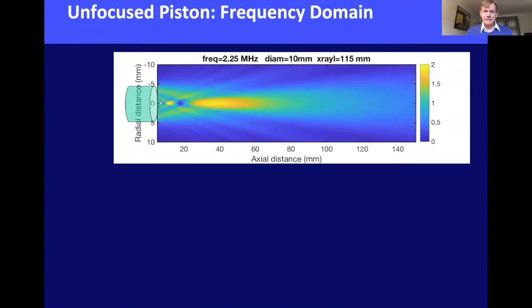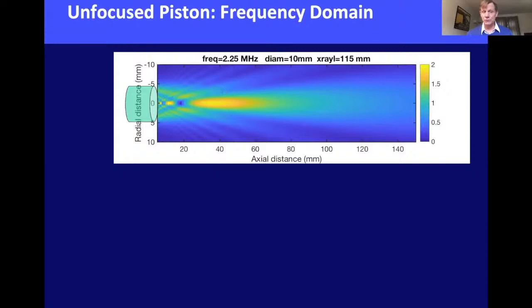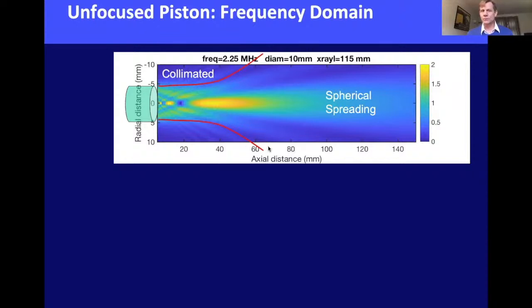For an unfocused piston in the frequency domain using the Rayleigh-Sommerfeld integral, an example for a 2.25 MHz transducer with 10 mm diameter shows a beam of sound emerging with spreading in different directions — not a simple plane wave. There is a near-field region where energy is collimated but with a complex pressure structure, and at greater distances the field transitions toward spherical spreading.